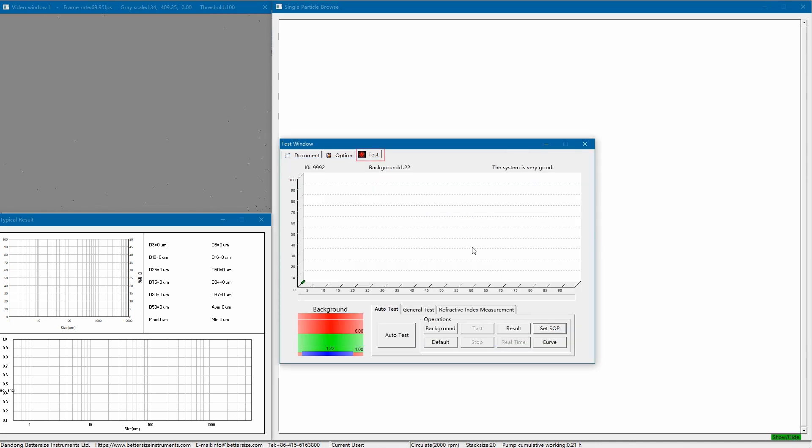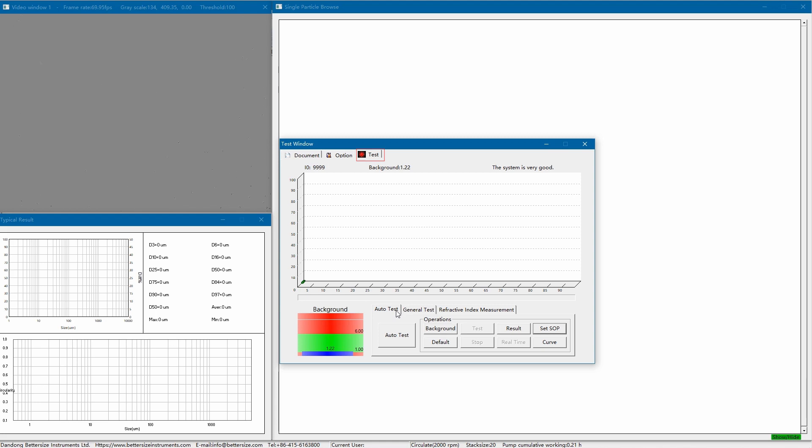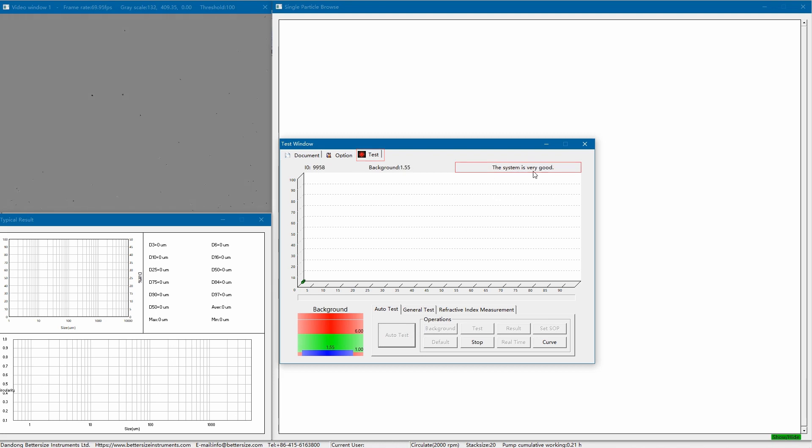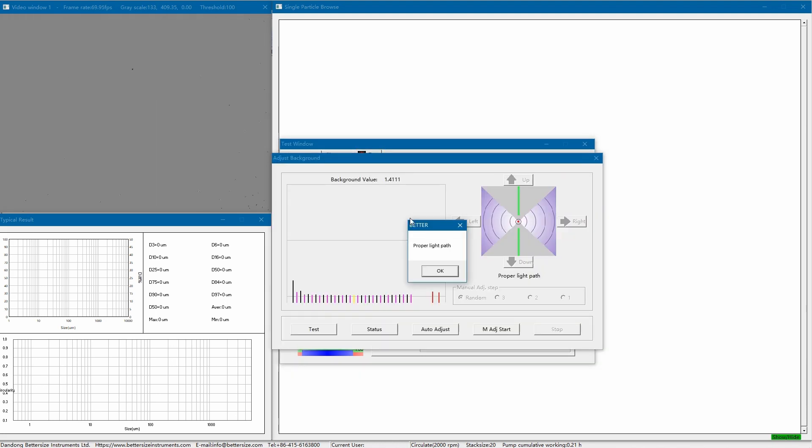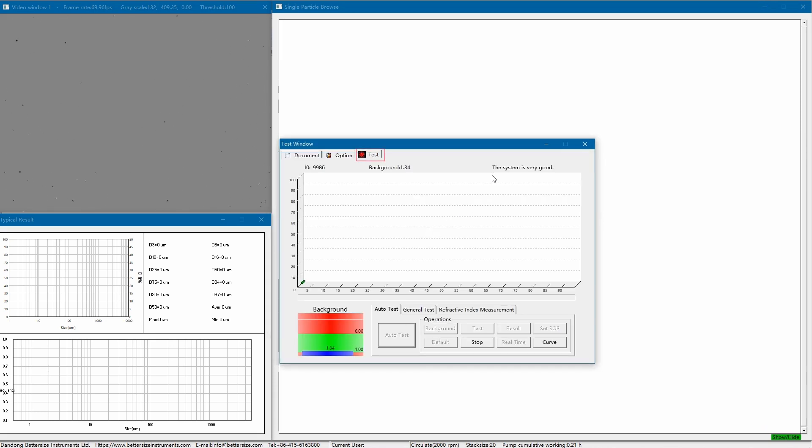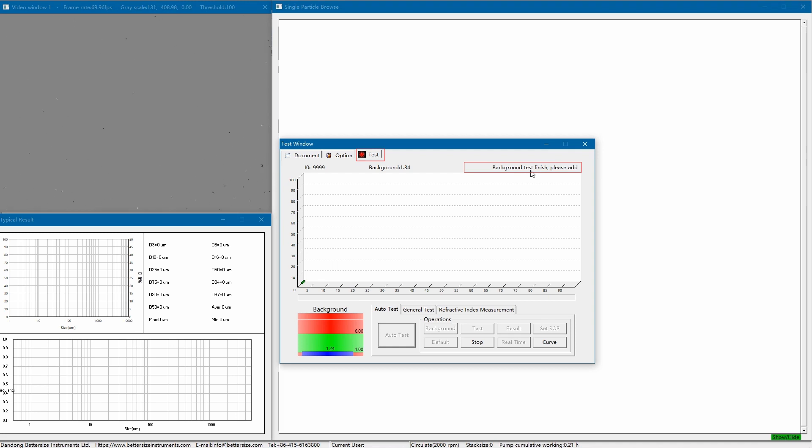In the upper right corner, the current status of the analyzer is displayed here, and the system is good and ready to go, so we can start the measurement at any time. The auto test of the Bettersizer F3+ is a smart and automated function. All you need to do during the measurement is to click Auto Test button and add sample once. Then the detailed and comprehensive results will be given. Let's click on the Auto Test now. The upper right corner here shows the progress of the test. The first one is level sensing and water, and the instrument starts to automatically adjust background that ensures the system is always in an optimal state. Then testing background. When it indicates background test finish, please add sample. We proceed to the next step, adding samples.